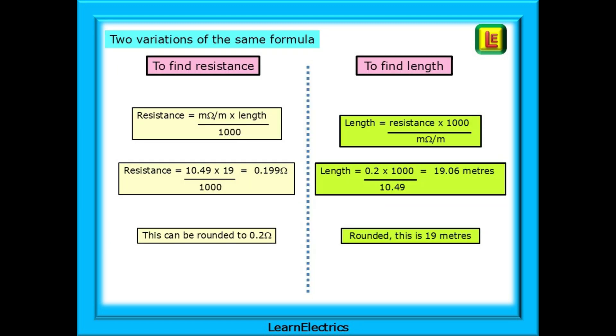We can now use a very easy formula — there are two variations. We can find the total resistance of the cable if we know the milliohms per metre and the cable length. By rearranging the same formula we can find the length one way if we know the measured resistance in ohms and the milliohms value for that particular combination of conductors. The formula tells us that 19 metres of 6x2.5 twin and earth should return a low ohms reading of 0.2 ohms after rounding. Using the same data we can calculate the length and we have a rounded figure of 19 metres one way.